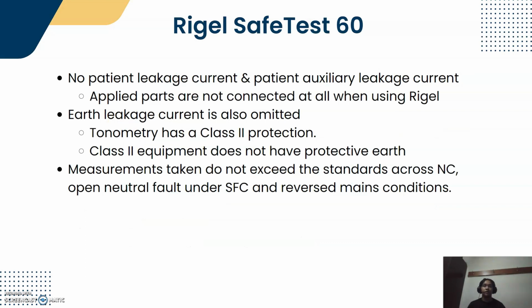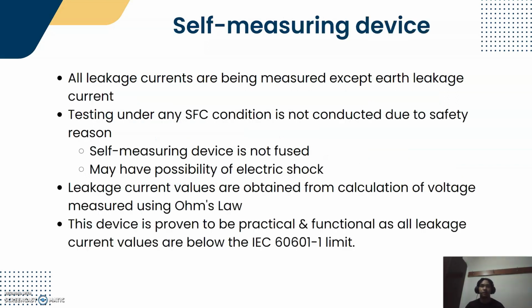Moving on to the Rigel Safe Test 60 Analyzer, there are no patient leakage current and patient auxiliary leakage current values at all because applied parts are not connected when using the Rigel. Earth leakage current is also omitted because the tonometry is a Class 2 device, and measurements taken do not exceed the standards across normal condition, open neutral fault under single fault condition, and reverse mains condition.